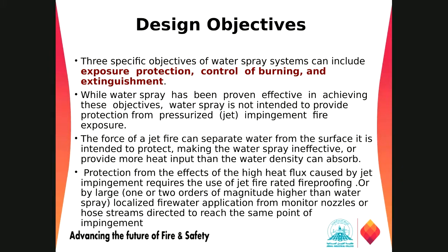Moving on to the design objectives, right? So we have three objectives for design with the water spray system: we have exposure protection, we have control of burning, and extinguishment. Most of the time when you are using a deluge valve water spray system for protecting your tanks, it is for exposure protection in most cases. And sometimes it will be control of burning and maybe for final extinguishment also.